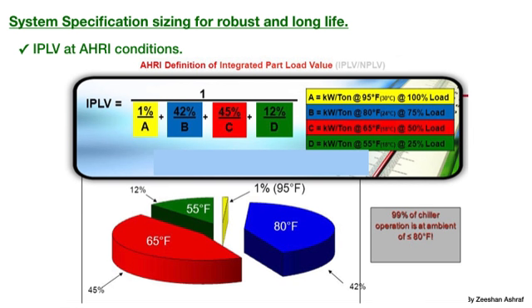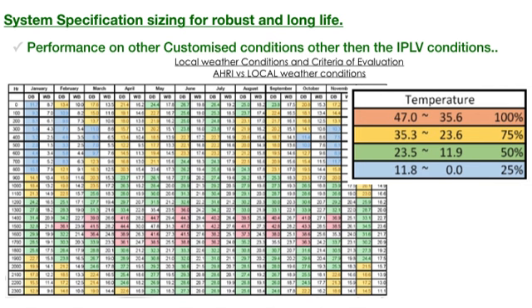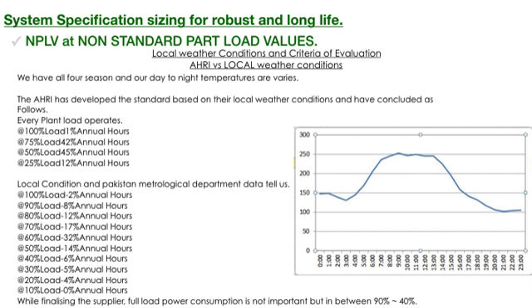Integrated part load values, IPLV, as per the AHRI 550-590 standard, are followed by the manufacturer for equipment performance check. No equipment operates at 100% capacity throughout the year, but almost always at part load. The higher the IPLV, the more the energy saving. We compared AHRI 550-590 with the local ambient profile, so we put each and every hourly ambient temperature into the load calculation software and ran the energy analysis feature on version 4.9 of HAP software. In conclusion, while finalizing the supplier, full load power consumption is not important, but the range between 90% and 40% is.